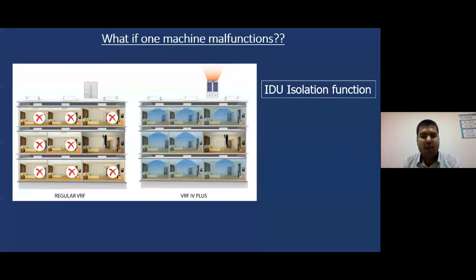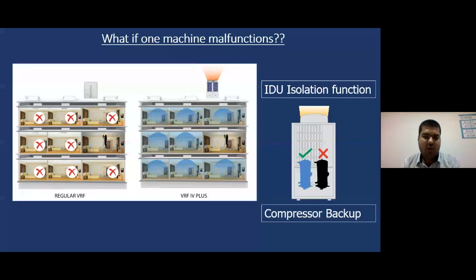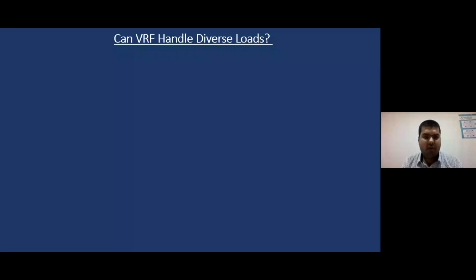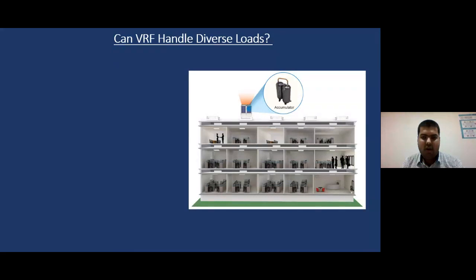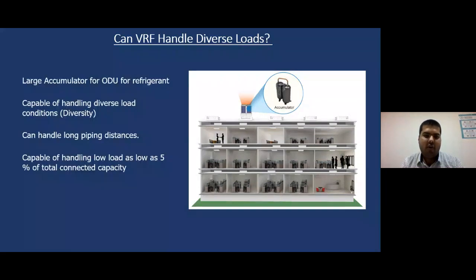Also, suppose my outdoor unit does not work, what would happen? In every outdoor unit, there are multiple backup compressors as well. If anything goes wrong with one compressor, my other compressor can very well handle it. So can VRF handle diverse loads? Suppose this entire building has a requirement of 100 tons and the occupancy was only these 2 rooms, will VRF work to its full capacity? The answer is no. The VRF would only work to the requirement of that room. Suppose these 2 rooms form a load of 4 tons or 6 tons, my VRF would only operate for that much load. So how does it do that? My VRF outdoor unit has an accumulator.